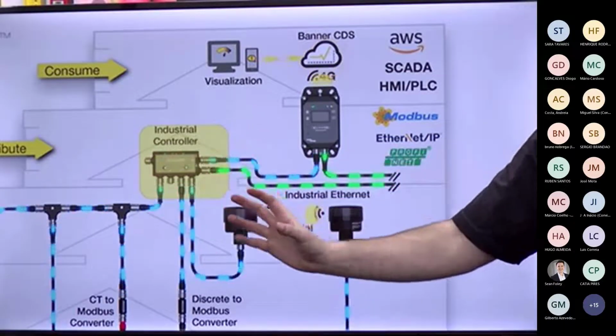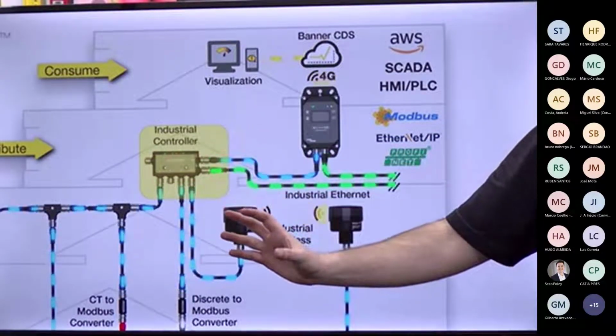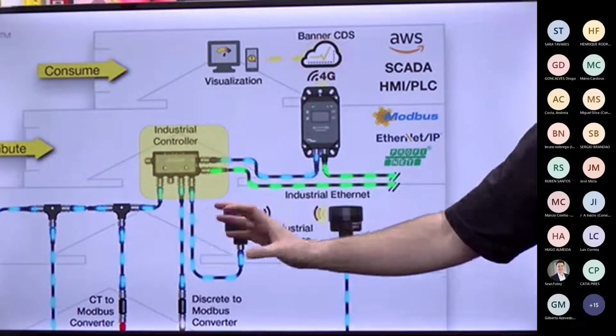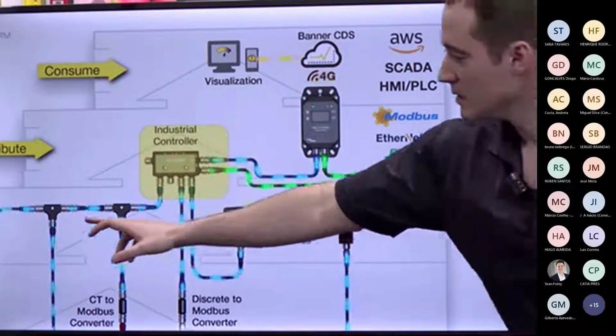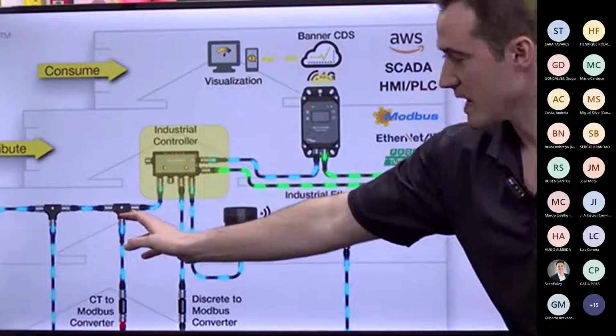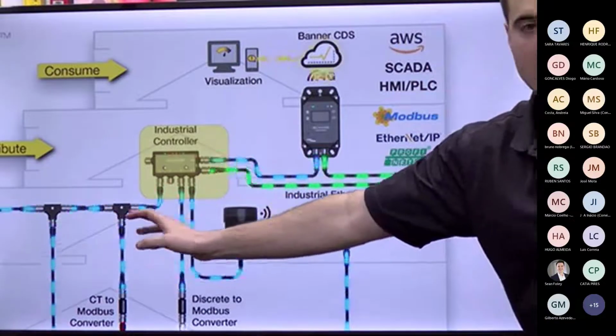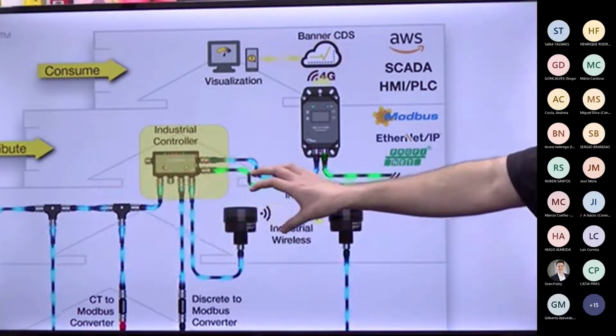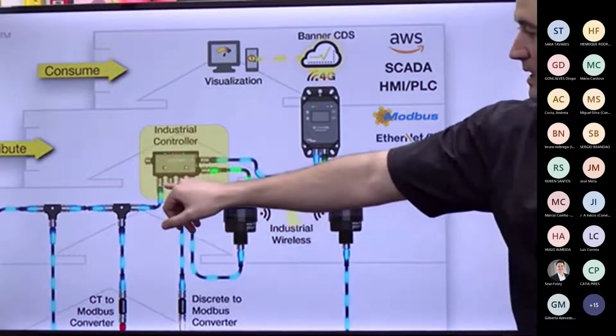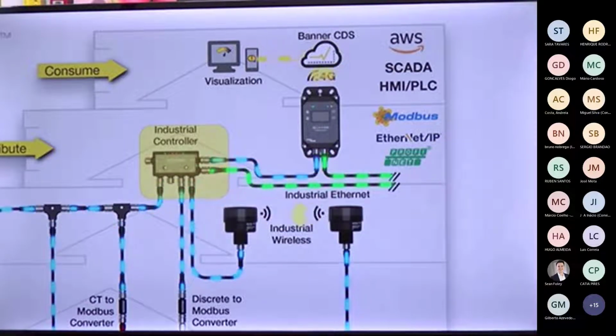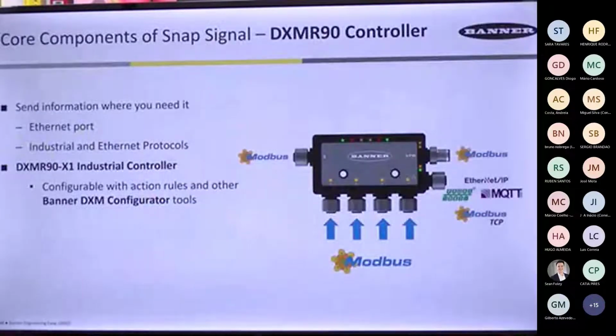With RS-485 or Modbus RTU protocols serving as the method for gathering the data, you could do trunk and branch methods. You could have a parallel wired M12T allowing you to bring in lots of sensor signals onto a single port of the DXM R90. So let's talk some specifics.